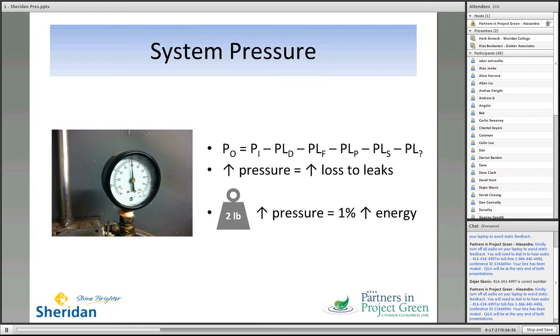Now, one of the nasty bits about pressure drops is that cumulatively, they rob your end uses of the power they need to perform effectively. And what ends up happening more often than not is the master regulator pressure is turned up. So now we've increased the amount of pressure in the system to try to compensate for pressure drops that could have been handled in other ways.